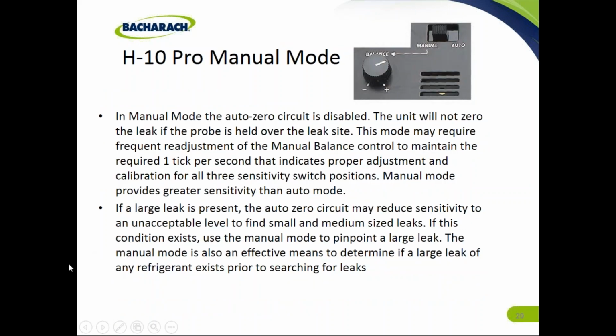In the manual mode, the auto zero circuit is disabled. The unit will not zero the leak if the probe is held over the leak site. This mode may require frequent readjustment of the manual balance control to maintain the required 1 tick per second that indicates proper adjustment and calibration for these 3 sensitivity switch positions. Manual mode provides greater sensitivity than the auto mode.